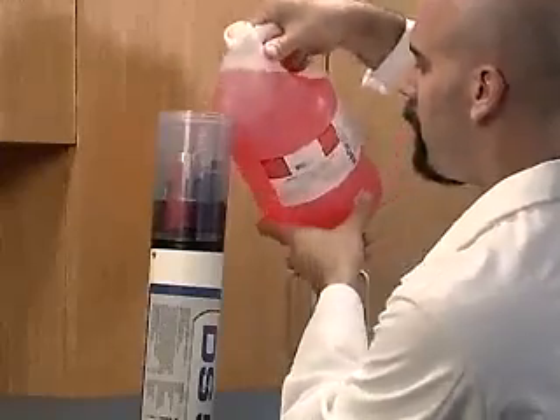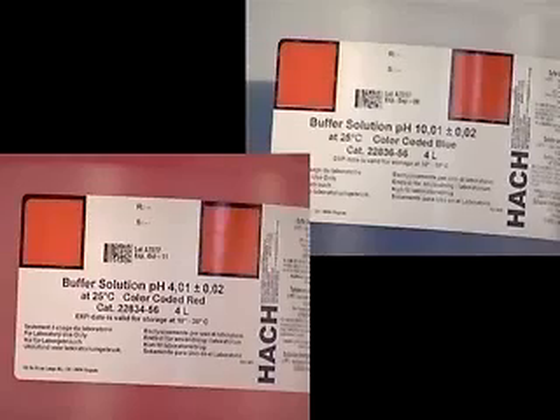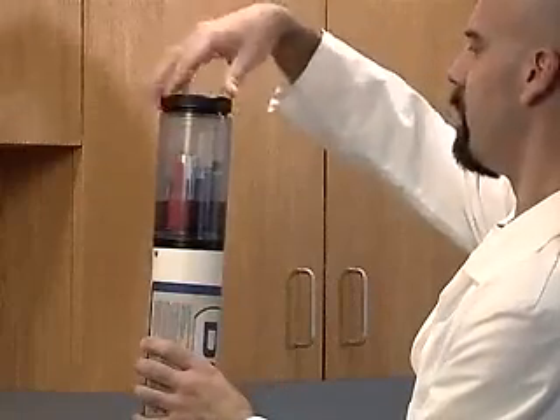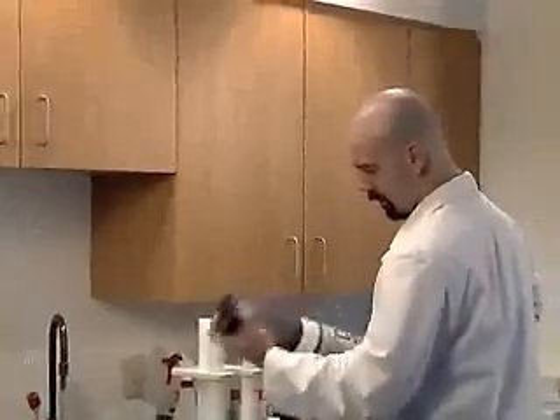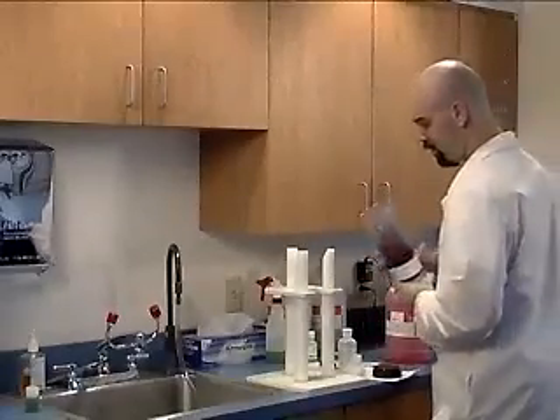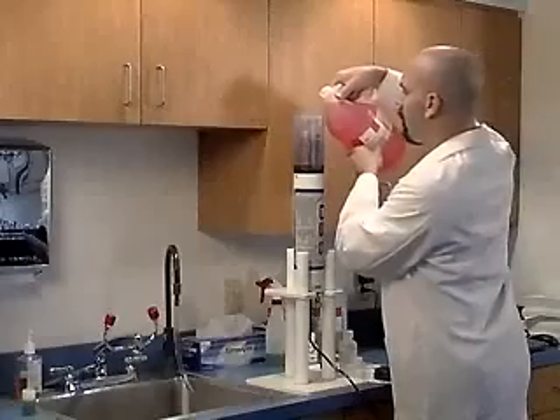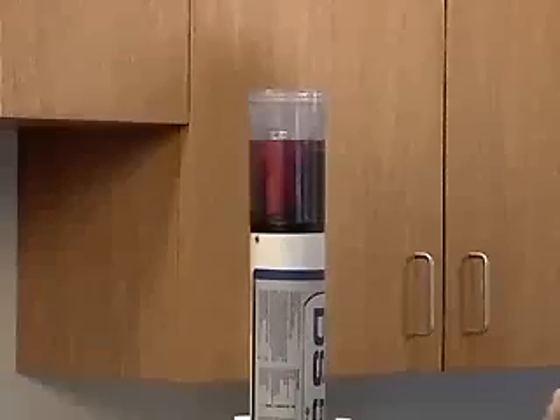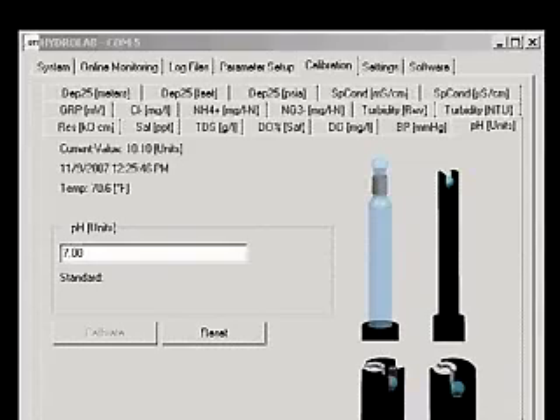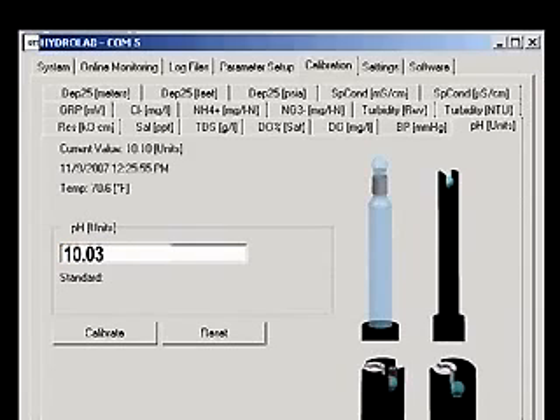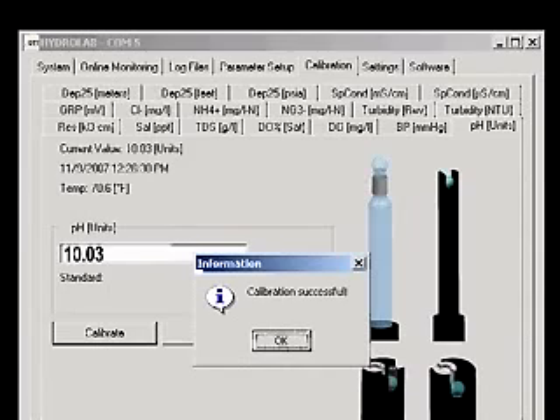Fill the cup about 25% with pH 4 or 10 buffer solution, depending on your expected deployment conditions. Screw on the storage cap and shake for 6 seconds. Remove the storage cap and pour the buffer solution out. Fill the cup with buffer solution again, this time over the top of the pH sensor. Wait 1 minute for the readings to stabilize. When the reading stabilizes, type the labeled value of the solution into the box, adjusted for temperature, and click Calibrate. A calibration successful message will appear.